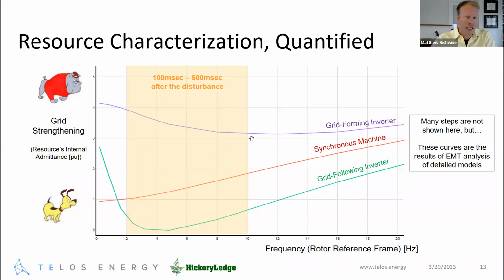So what we see here is that the grid forming inverter is supporting voltage. It's applying a fair amount of effort, and it's doing that in all of the relevant timeframes that I would consider for large system stability. This shows that the quality of voltage regulation from this example grid forming inverter is higher than that of this example synchronous machine and this example grid following inverter.